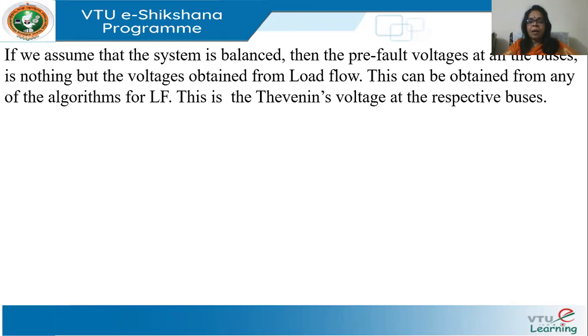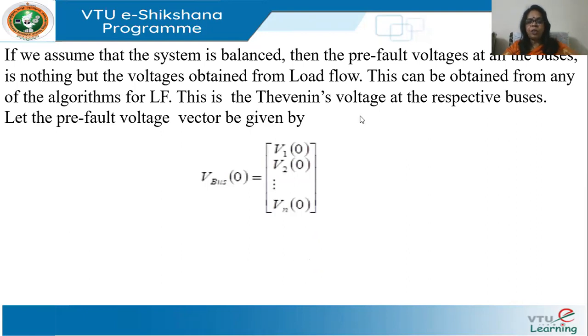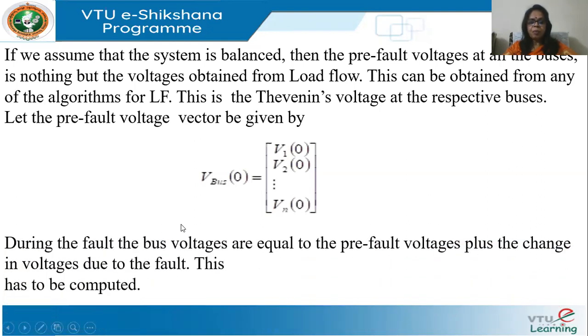Whichever bus you are going to simulate a short circuit at, the voltage at that bus obtained from the load flow study is the Thevenin's voltage of interest. I write the entire pre-fault voltage vector as V_bus_0 = [V1_0, V2_0, ..., VN_0]. This is nothing but the vector of bus voltages obtained from the load flow studies.